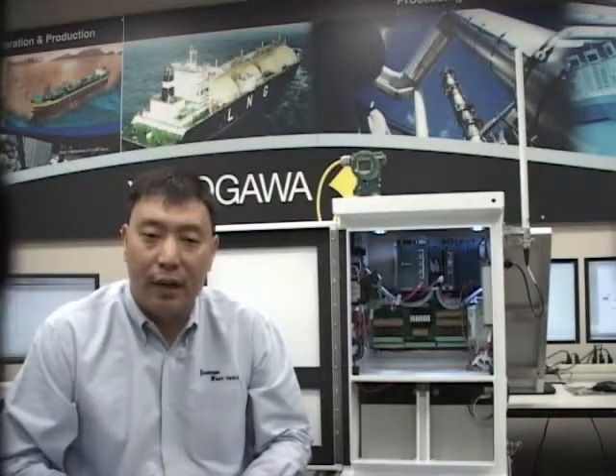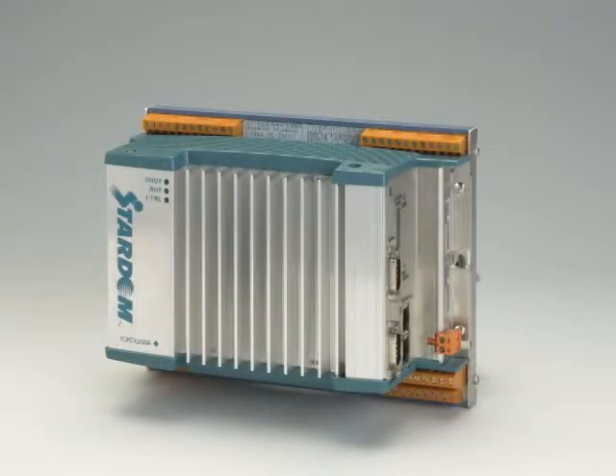Let's take a close look at STARDOM. First is FCJ. It has two Ethernet ports, which can connect to two different networks or be teamed together as a redundant network connection. It has a fixed number of traditional IOs, two Foundation Fieldbus segments, and two built-in DE9 ports for serial connections, such as Modbus RTU. FCJ is suitable for process applications with small amounts of IOs, for example, wellheads.